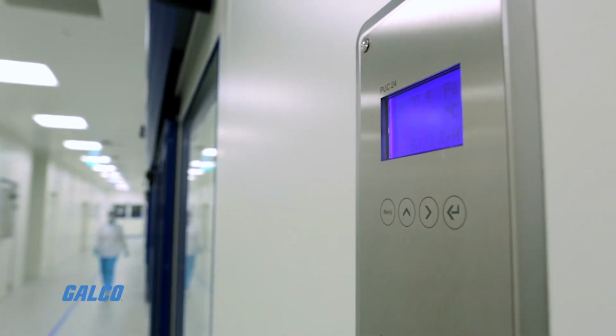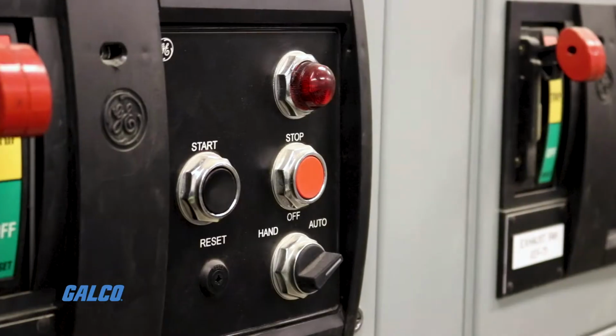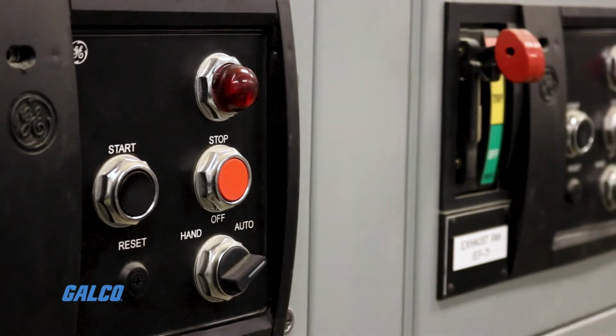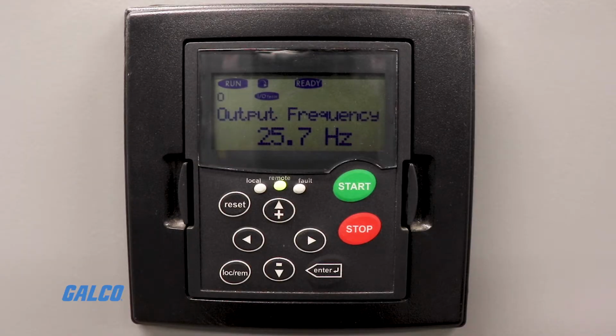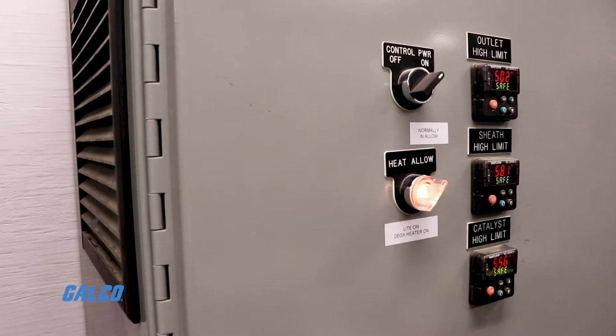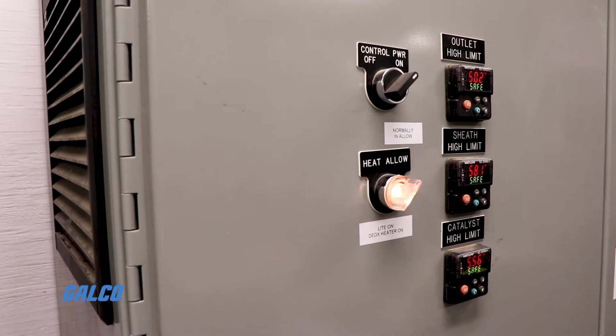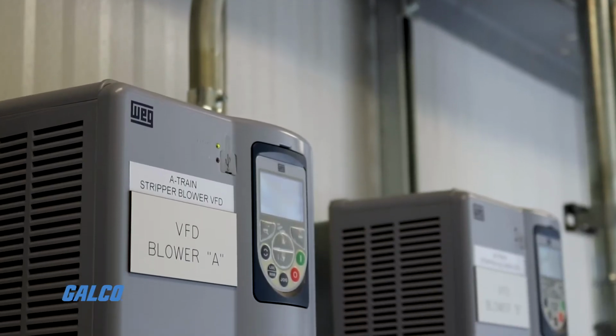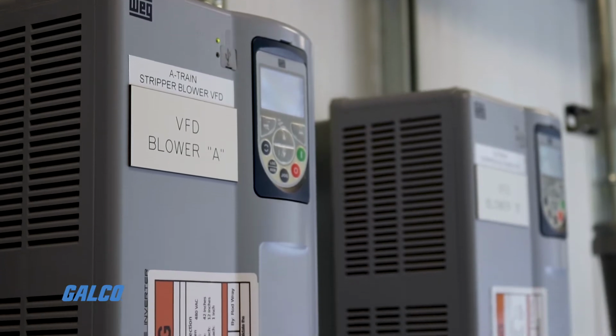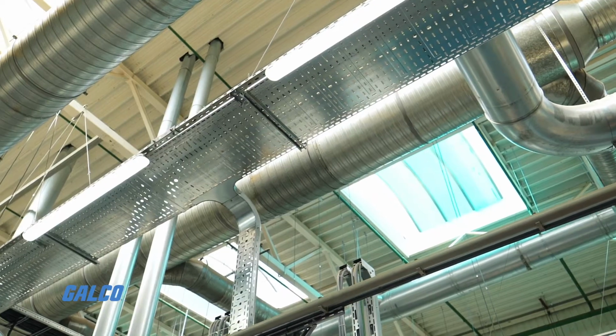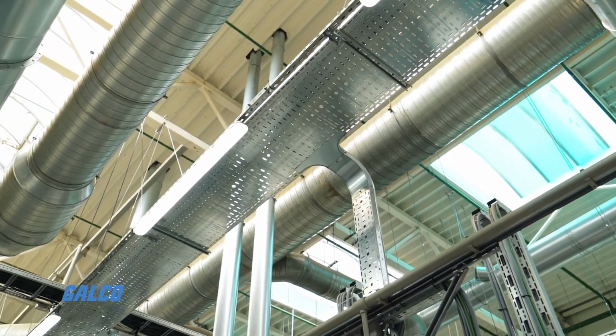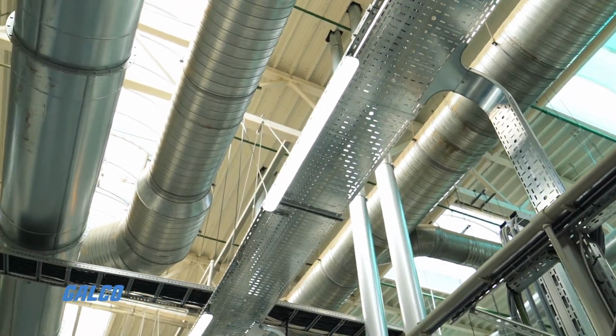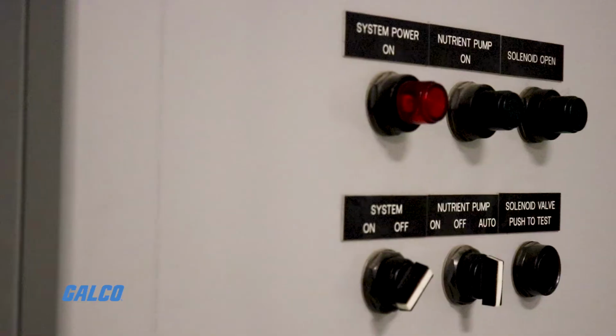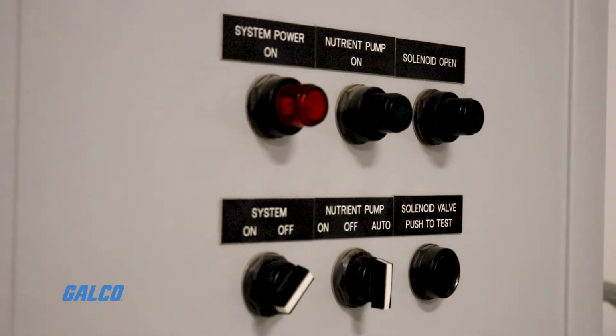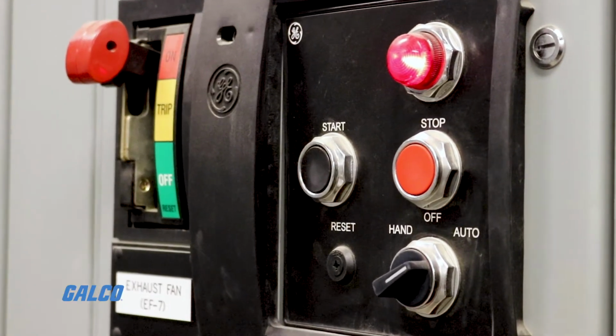Variable frequency drives provide three key benefits to air handling unit operation: startup control, torque acceleration and speed control, and equipment efficiency. In each case, the VFD decreases wear and tear on your motors, extends the life of your equipment, reduces energy consumption, and simplifies maintenance in case a shutdown occurs, so that you can get back to business quickly.